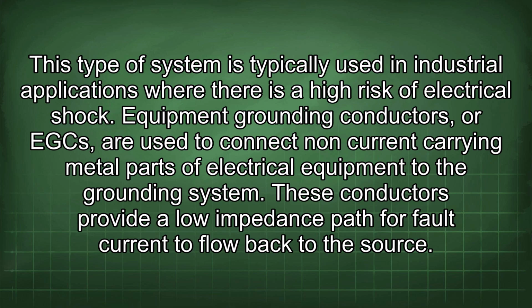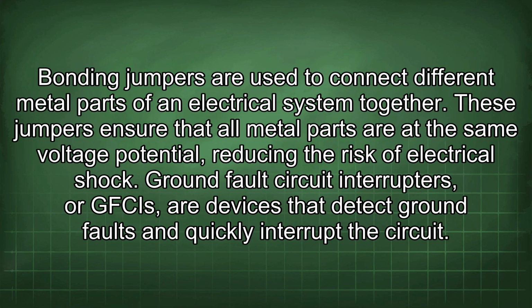Equipment grounding conductors, EGCs, are used to connect non-current carrying metal parts of electrical equipment to the grounding system. These conductors provide a low impedance path for fault current to flow back to the source. Bonding jumpers are used to connect different metal parts of an electrical system together. These jumpers ensure that all metal parts are at the same voltage potential, reducing the risk of electrical shock.